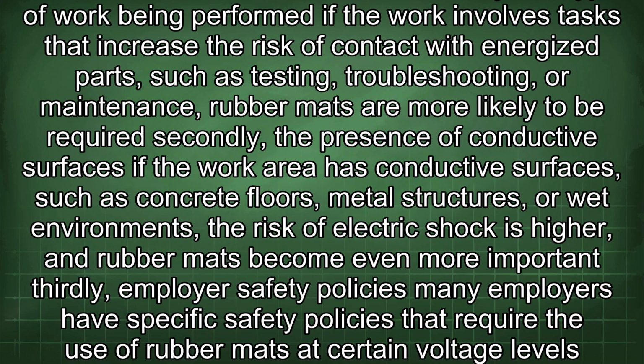In addition to voltage level, other factors also influence the need for rubber mats. Firstly, the type of work being performed. If the work involves tasks that increase the risk of contact with energized parts, such as testing, troubleshooting, or maintenance, rubber mats are more likely to be required. Secondly, the presence of conductive surfaces. If the work area has conductive surfaces, such as concrete floors, metal structures, or wet environments, the risk of electric shock is higher, and rubber mats become even more important.